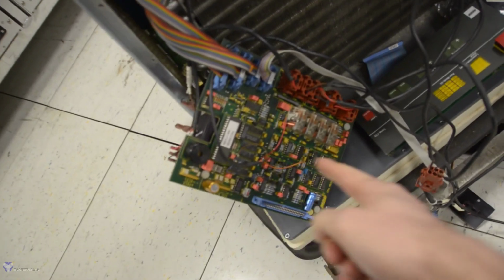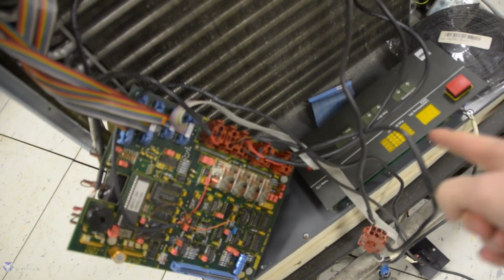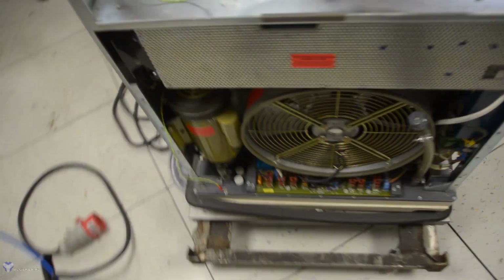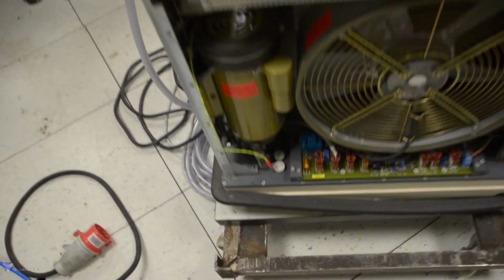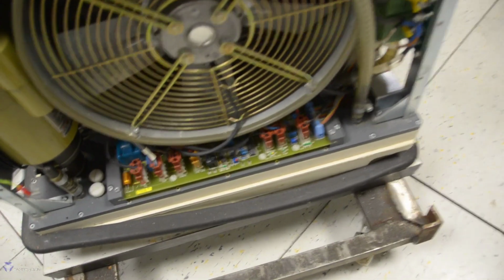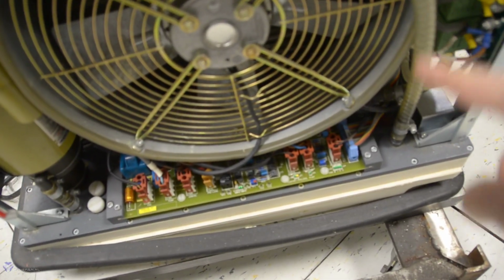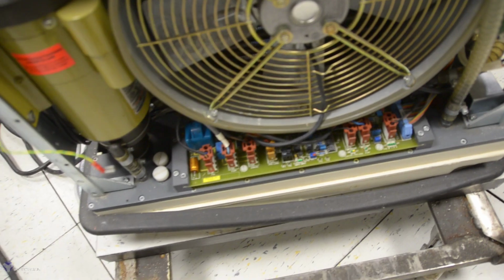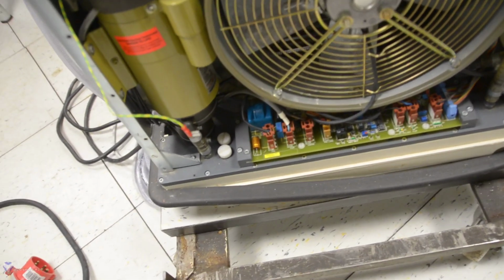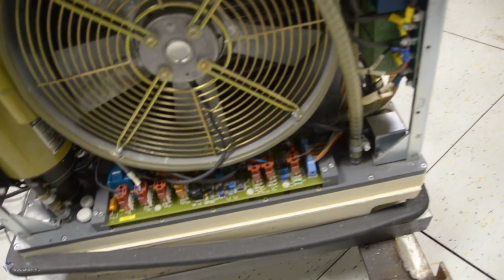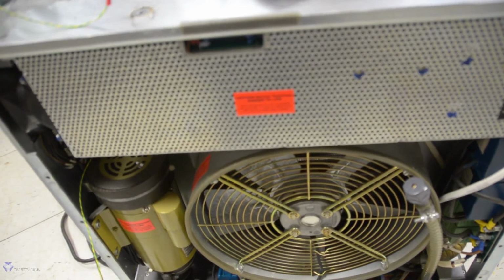This is the main PCB, that's the front panel with all of the controls. See the big radiator with here the high voltage power supply that powers the arc lamp. And if we look in the back, you see the big fan and the water cooling pump. And the reservoir sits in the bottom of the laser. This is the filling tube, and the whole bottom of the laser is the water reservoir. And there are some more electronics around here, but nothing exciting.